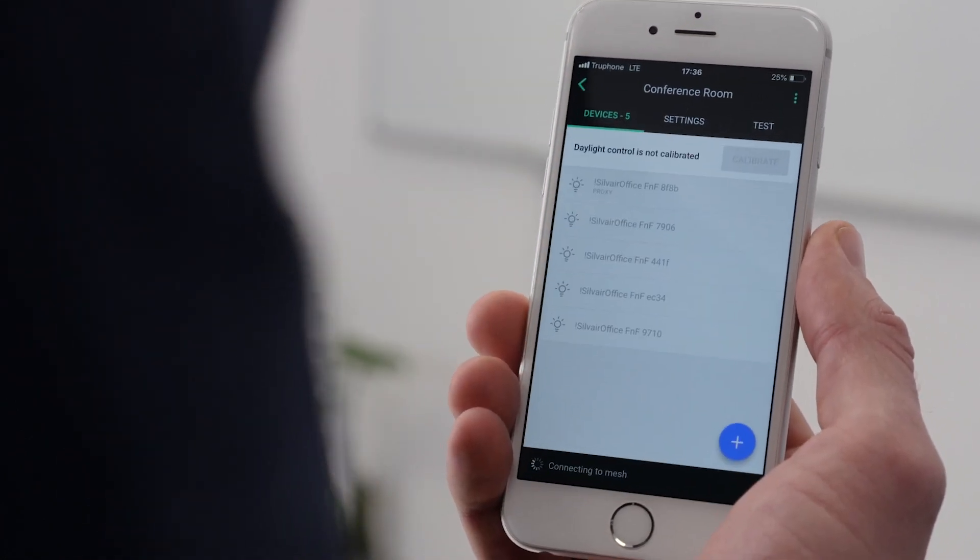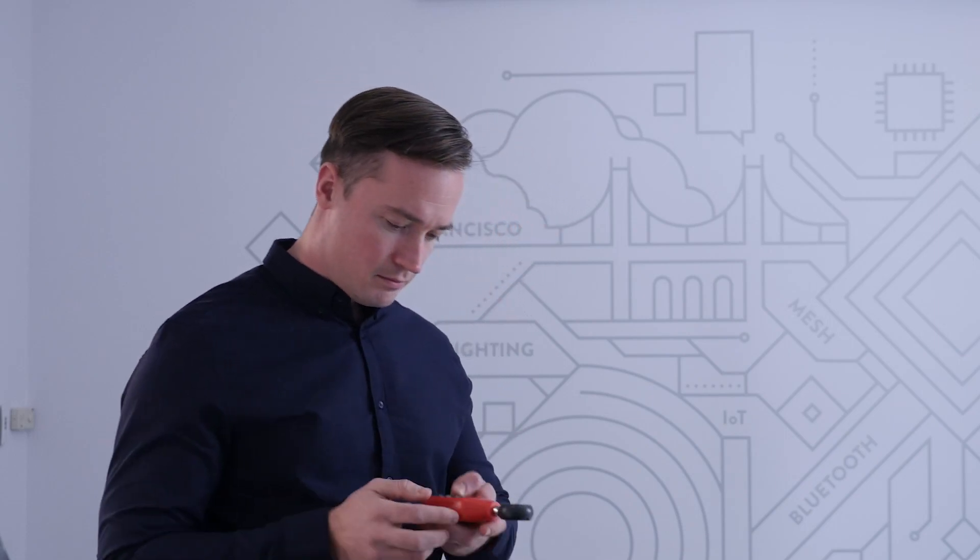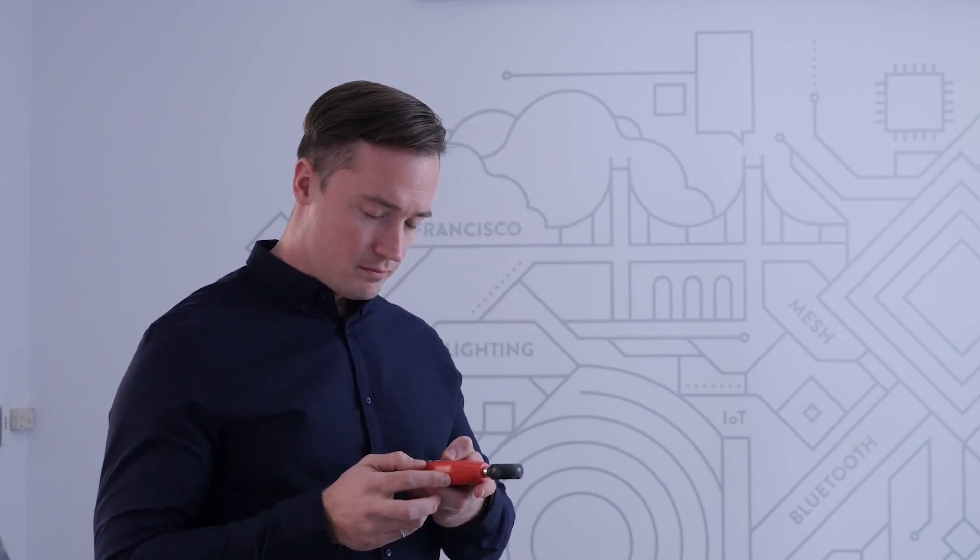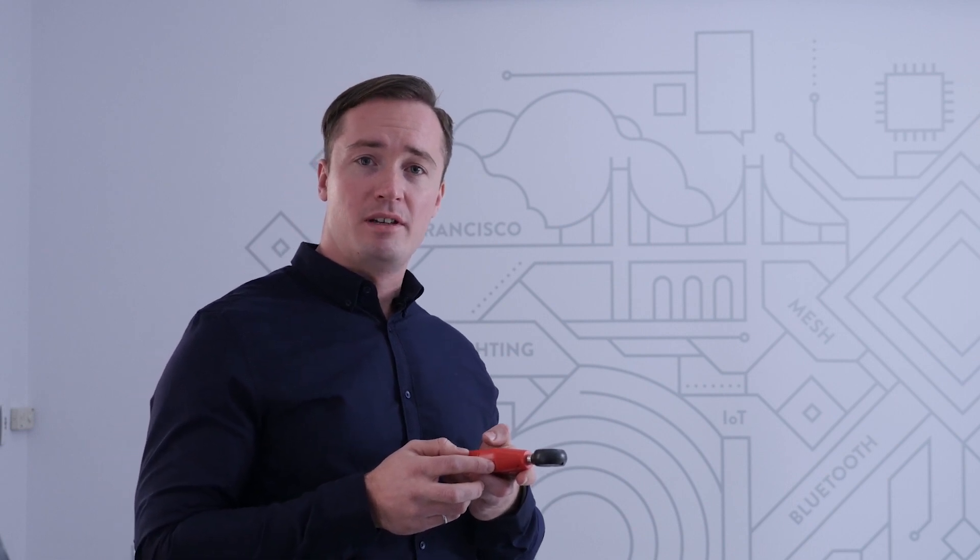The conference room profile that we chose uses occupancy sensing and daylight harvesting strategies, which requires us to calibrate the ambient light sensor. First, let's identify the sensor we'd like to use by selecting it in the app. Next, let's take a light meter and measure the level of light in the room. We'll now input this value into the app to complete the calibration process.